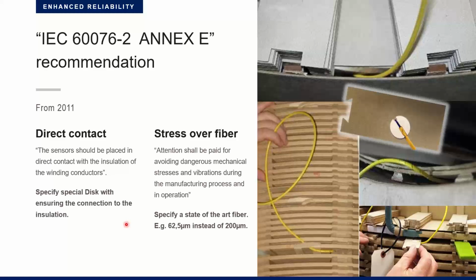I would just recommend you to look into the IEC 60076-2 Annex E, which was introduced in 2011. Before you specify fiber optic temperature sensors, go through it. It's about 3-4 pages, and there's a lot of interesting stuff mentioned there.